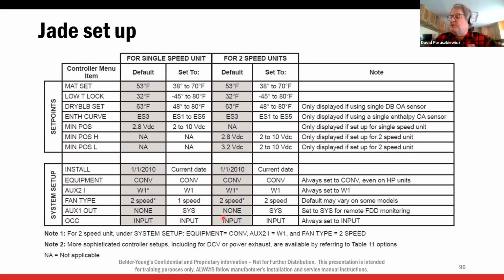Then occupancy input, we're going to leave that alone. So these are pretty cool to set up, pretty simple to set up. Some of the biggest things I've seen an issue is this low temp lockout is set too high and the compressors won't come on. That's been a big one, or this mixed air is jacked up. Okay, there's some settings in there for airflow, CFM. We're not using any of that, so don't mess with any of that. This is all you have to mess with on the Jade. Again, some of the support material you'll be receiving by email will include the setup instructions and things like that.